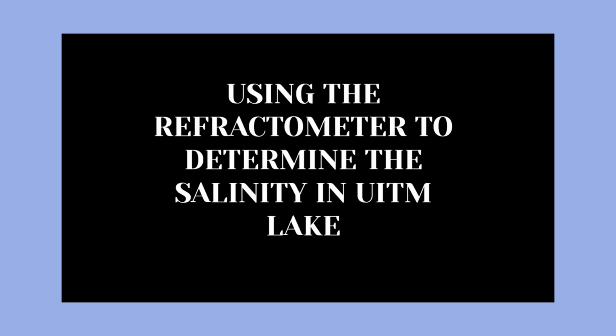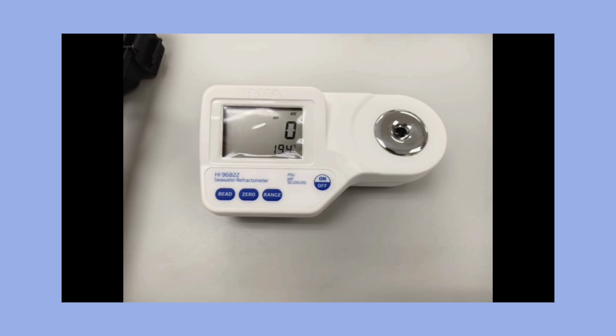Now we are going to use the refractometer to determine the salinity in UITM lake. Now this is a digital refractometer. To use it, firstly we have to turn it on, and then we have to clean the scanner with distilled water and then wipe it with a clean cloth. Now we have to press read until it's calibrated to 0.